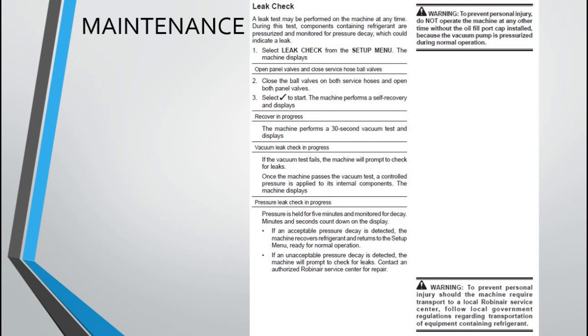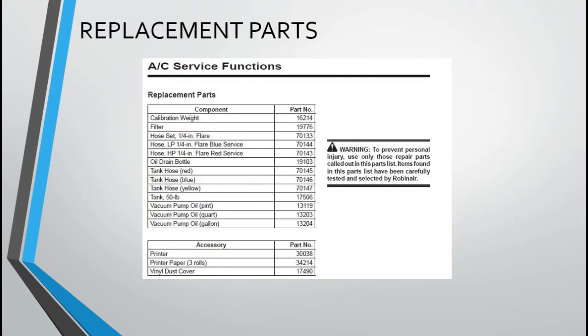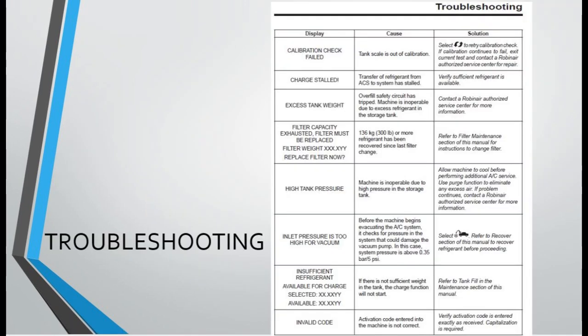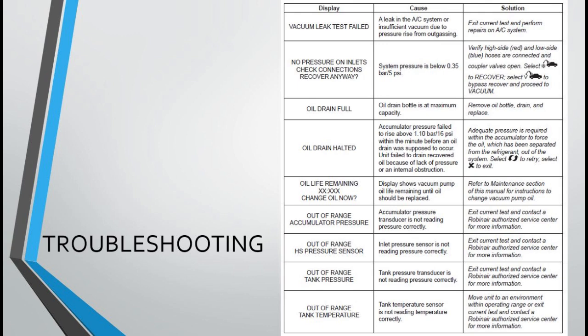If an acceptable pressure decay is detected, the machine recovers refrigerant and returns to the setup menu, ready for normal operation. If an unacceptable pressure decay is detected, the machine will prompt to check for leaks. Contact an authorized Robinair Service Center for repair. See the table for components and part numbers for any replacement parts that will be needed. A troubleshooting guide is also available for the equipment. The display will indicate an issue, and the cause and related solution will be found in this table. See manual for complete table.